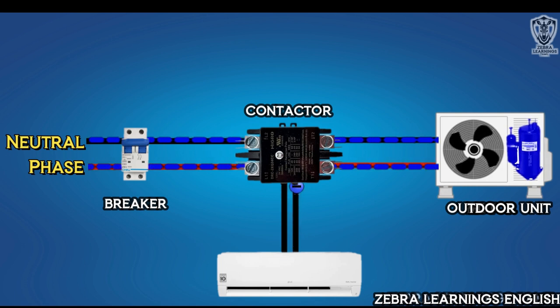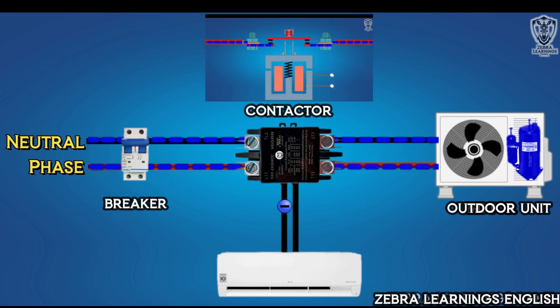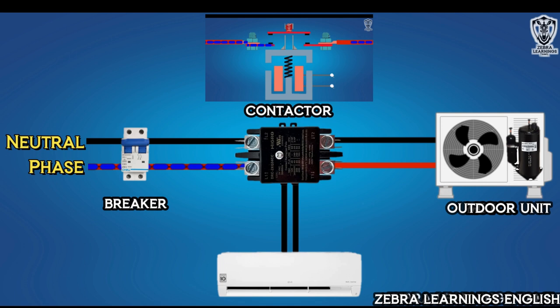After the room temperature reaches the set point, the indoor unit will cut off the 24-volt power supply. Then, contactor terminal will come to normal position and outdoor unit will be cut off. This is how the contactor works.